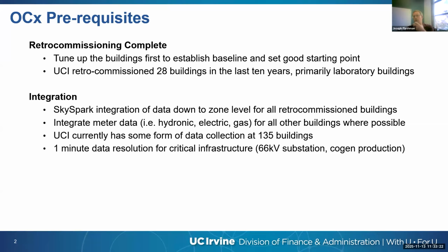One of the things that we do, we also use SkySpark. We integrate our data down to the zone level for all of our retro commissioned buildings. So, you have laboratory buildings with variable air volume, supply and exhaust and fume hood valves. All of that data is pulled into SkySpark, and we can use that to continue to keep an eye on how the buildings are operating and make adjustments as necessary.